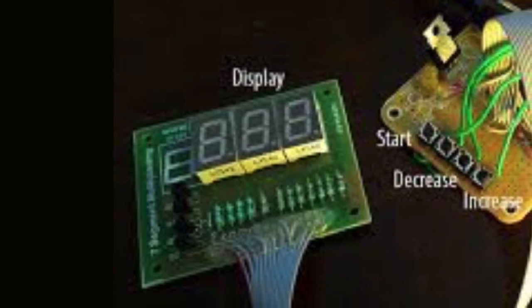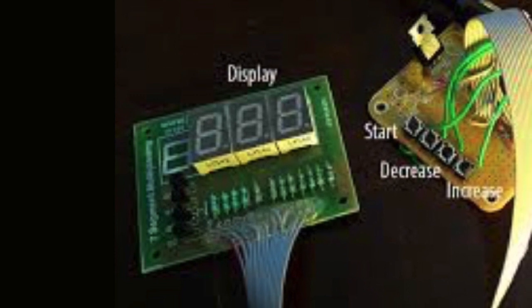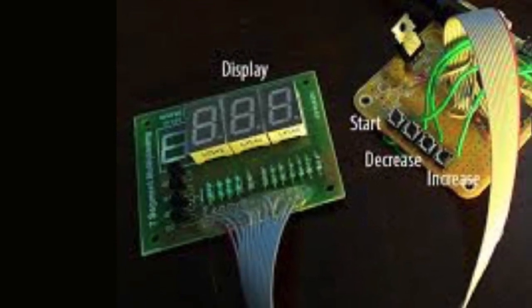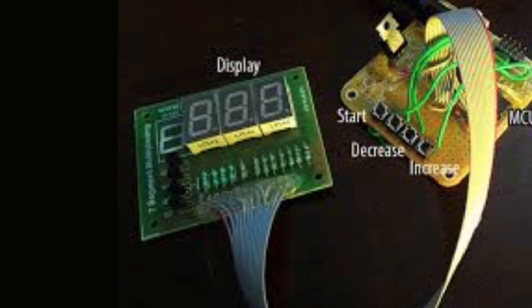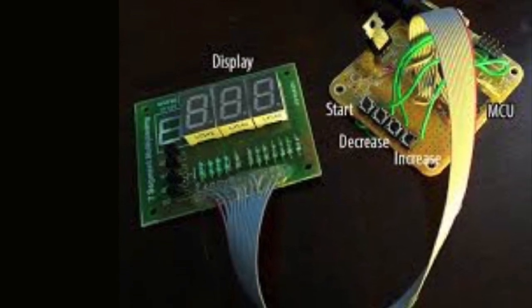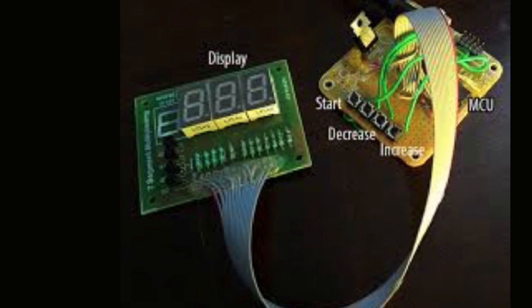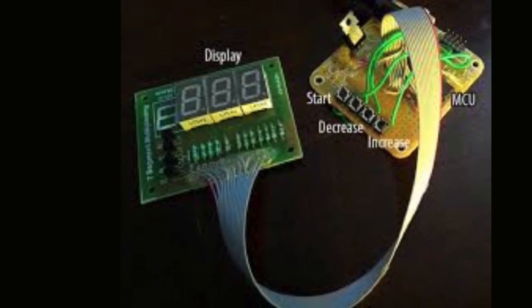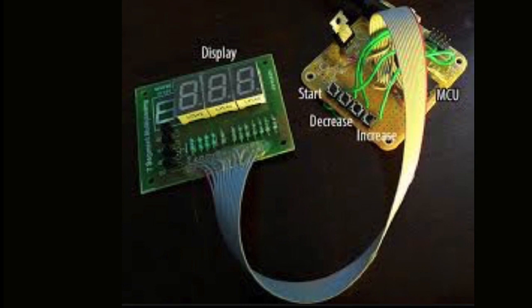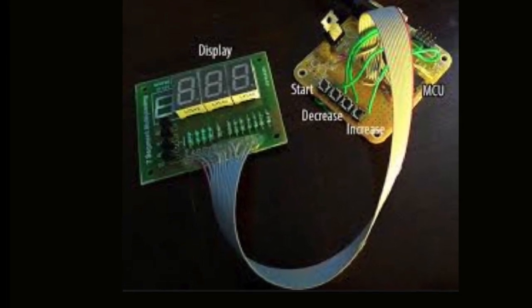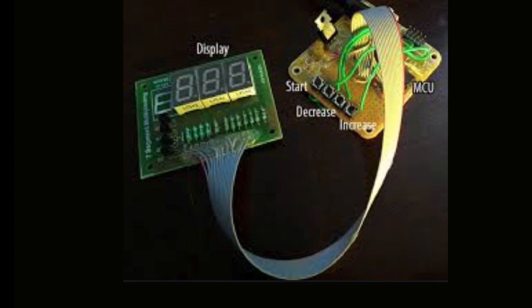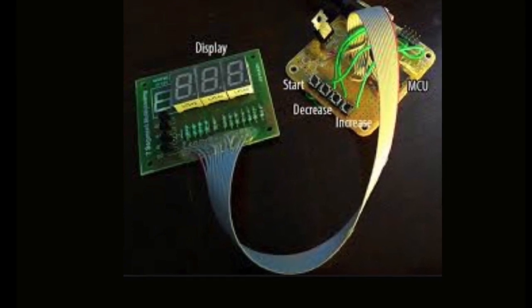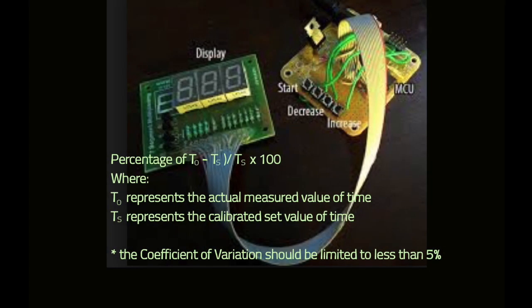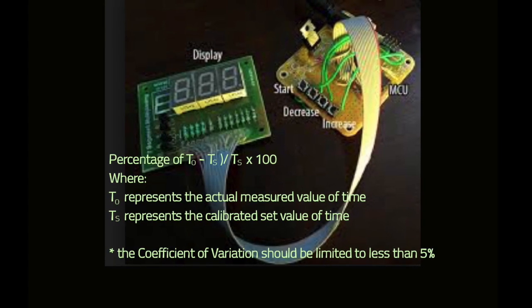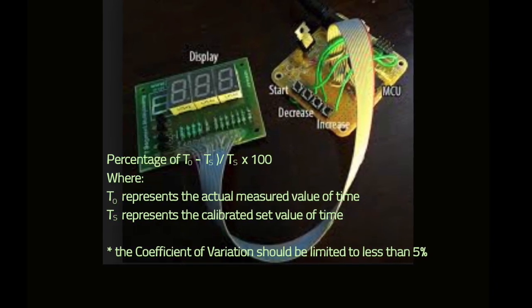The accuracy of the timer has a direct relationship with patient dose. As previously mentioned, the timer shares an inversely proportional linear relationship to milliamperage when mAs remains constant. Remember, milliamperage times time duration equals mAs. Therefore, in considering the testing and calibration of mAs, the timer should be evaluated first. The most efficient way to test time is with a computerized dosimeter, and the measured value should be within 5% of the labeled setting. The following equation can help you calculate the percentage of timer error.